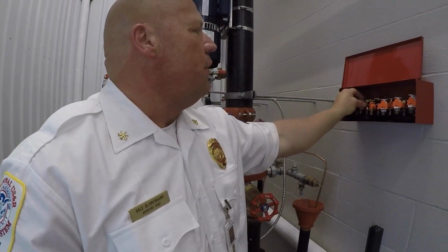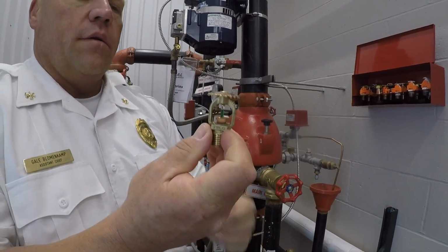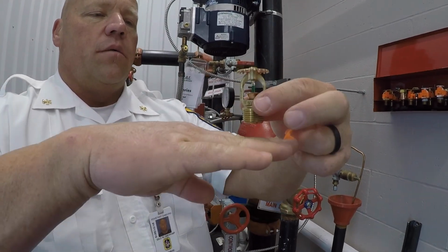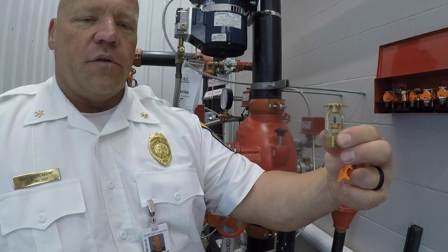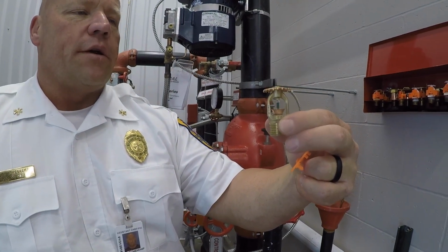And then you have an upright sprinkler head. So again, green for 200 degrees. The sprinkler head is designed to sit like this. So water hits this deflector and forces a fan of water to come out in 360 degrees, in that direction.